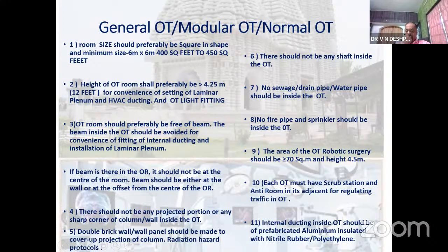The wall should be double brick. That is to consider the sound system. I mean, outside sound or inside sound should not go out. Radiation hazards have to be considered. No sewage or drainage pipe should pass through the theater. There should be no fire sprinklers in the operation theater. These days, the fire safety measures have become compulsory for every hospital. If you are going to convert your theater into a robotic surgery theater, you may have to consider a little more space.